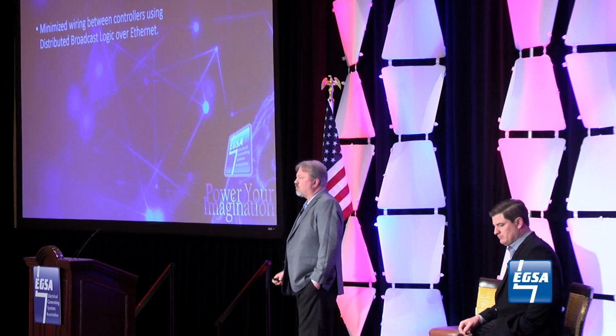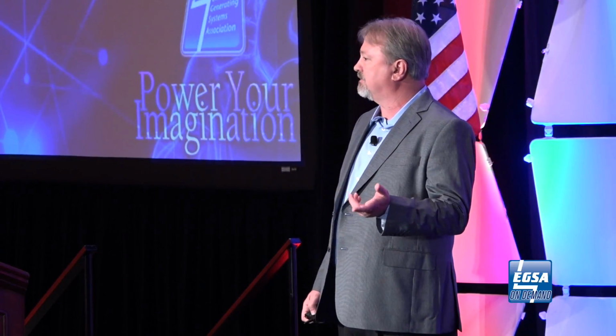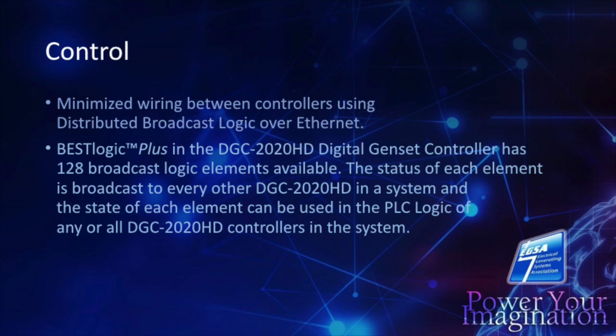We also minimize the wiring between the controllers. If you remember in the pictures we showed earlier, some of these generators are about 300 to 400 feet from the first set of bus tie breakers. And all of that interconnection, all the status signals, everything we have is sent over the Ethernet using distributed broadcast logic bits. In the BESTlogic in the 2020HD, we have 128 bits available, so it made it really easy to set this up.